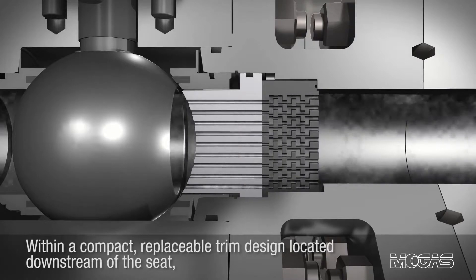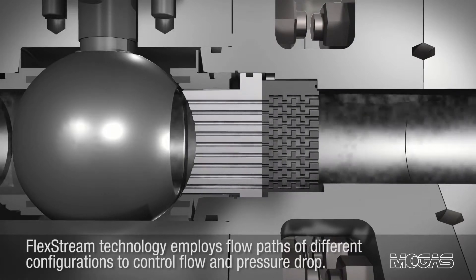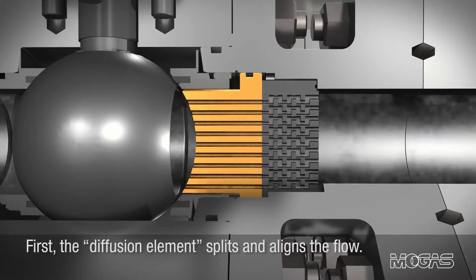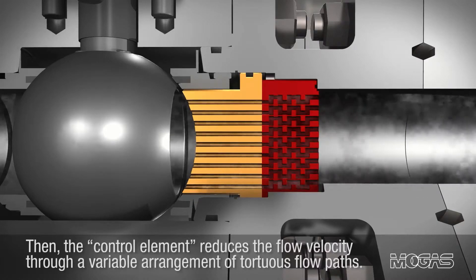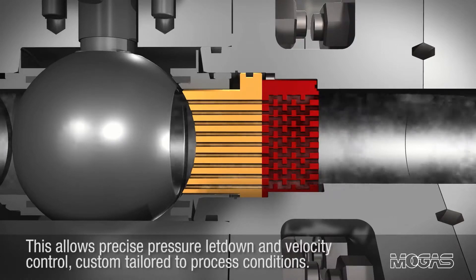Within a compact replaceable trim design located downstream of the seat, FlexStream technology employs flow paths of different configurations to control flow and pressure drop. First, the diffusion element splits and aligns the flow. Then, the control element reduces the flow velocity through a variable arrangement of tortuous flow paths. This allows precise pressure letdown and velocity control, custom tailored to process conditions.